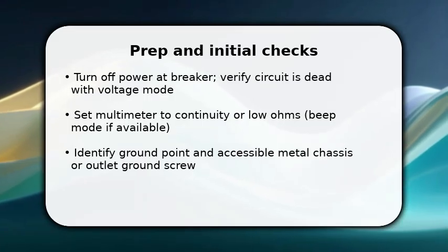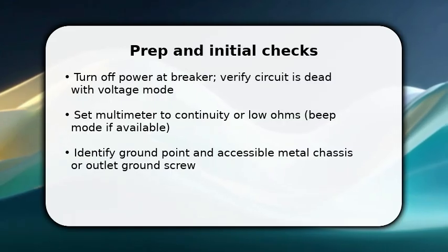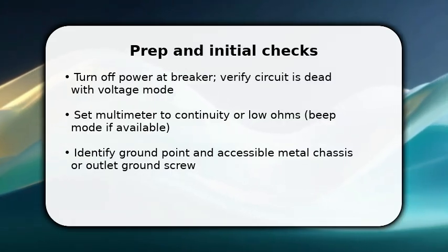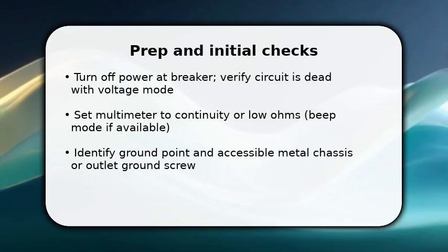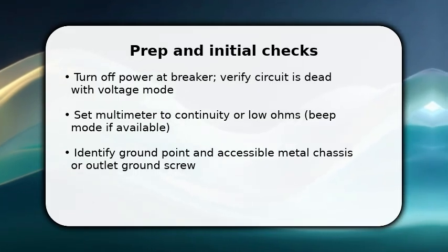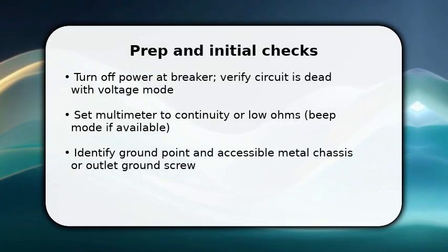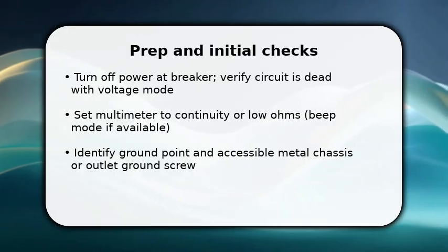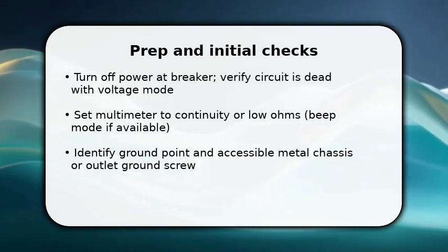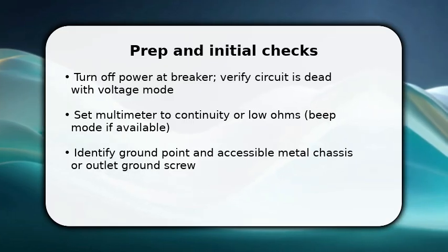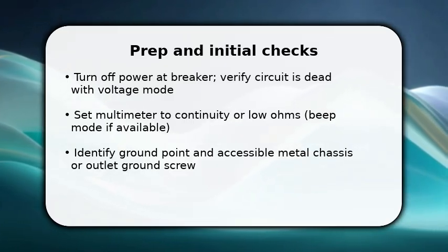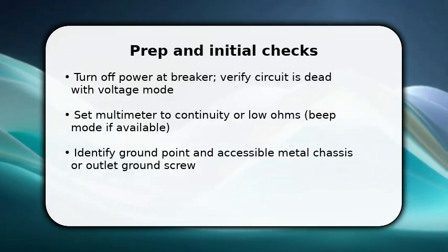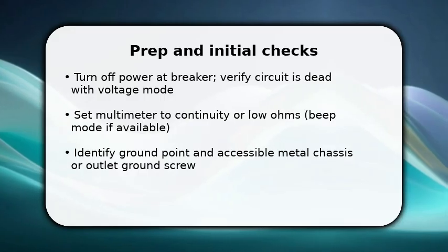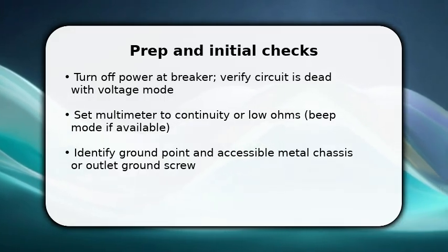You begin by cutting power at the breaker and confirming the circuit is dead with voltage mode, safety first. Next, set your multimeter to continuity or low ohm range so you get a clear beep or numeric reading when continuity exists. Inspect the device or outlet and pick a reliable ground point, typically the green screw, conduit, or metal chassis. Once done, expose the connections you'll test, but do not disconnect wiring unless required.